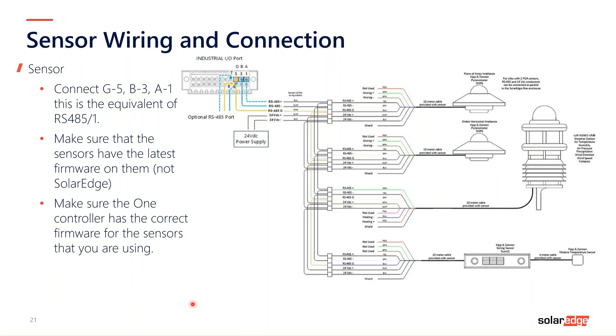Now, all this requires a little more firmware to work nicely. So we've got a picture here showing the latest firmware. This is where you'd expect to see it, either on SolarEdge Go, or on the inverter itself, though you can't see it directly, but we can see it internally. It's 4.24.509, and you need to make sure support updates these inverters to this version.